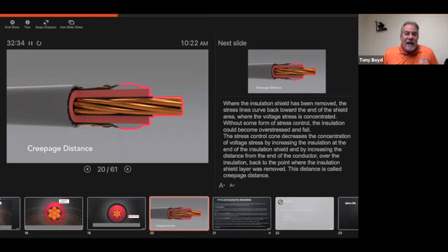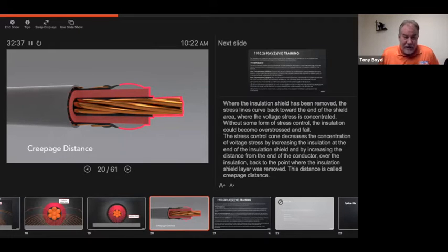And here we have one that is actually cut back thanks to some of our 3D illustrations. You can see the red insulation and the conductor, the semiconductor, the insulation, and then the semiconductor shield underneath those concentric wires. So basically, the stress when we cut off that insulation shield and we're terminating to make a splice or a terminator, it creates an extra stress going back over that semiconductor trying to go to ground, and the leakage current is exceeded. So we need to build up a stress cone.